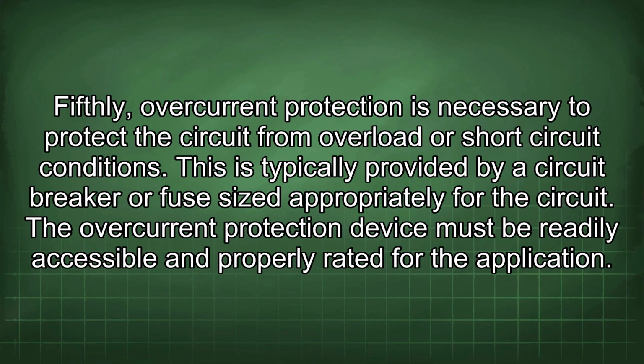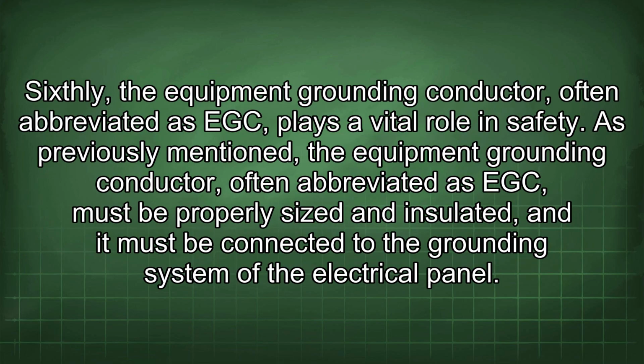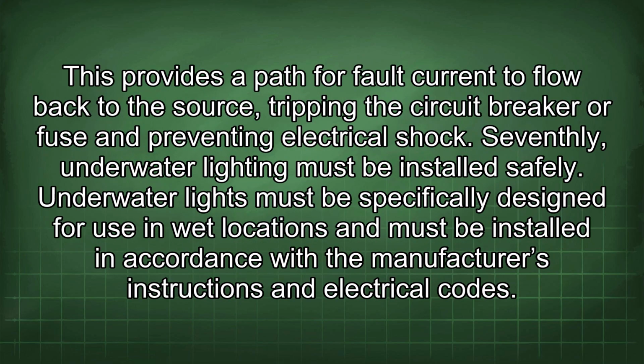Fifthly, overcurrent protection is necessary to protect the circuit from overload or short circuit conditions. This is typically provided by a circuit breaker or fuse sized appropriately for the circuit. The overcurrent protection device must be readily accessible and properly rated for the application. Sixthly, the equipment grounding conductor, or EGC, plays a vital role in safety. As previously mentioned, the EGC must be properly sized and insulated, and it must be connected to the grounding system of the electrical panel. This provides a path for fault current to flow back to the source, tripping the circuit breaker or fuse and preventing electrical shock.